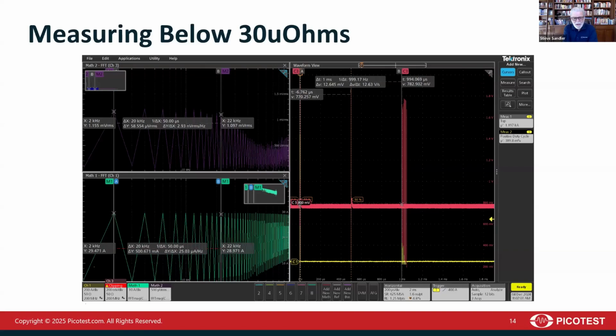We're doing that using time domain FFT data. On the right side, we're using one of our high-speed transient pulsers to generate impulses, and on the left side, we get FFTs of the voltage and current waveforms. Then we divide voltage by current to get impedance. One benefit of doing it this way is that we can do it incredibly fast. Another benefit is that the currents are really large — even using these impulses, you can see in the lower right corner we get about a 30 amp signal, and that 30 amps is independent of frequency because it's an impulse.